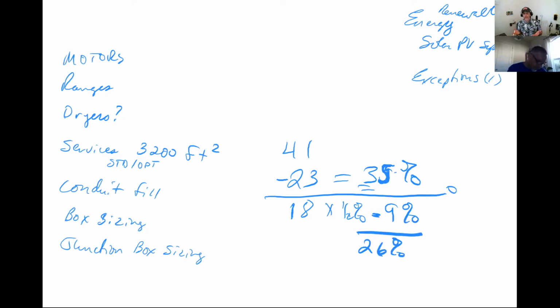Depending on what the question asks, I may still need to use this by going back to the 41 and multiplying that times the 5,000 nameplate value, then multiplying the 26% against that number to get the true demand load used to calculate the feeder size. So this number gives me a demand load I can use to size the wire in the service.